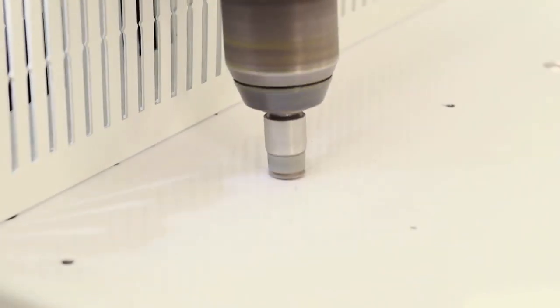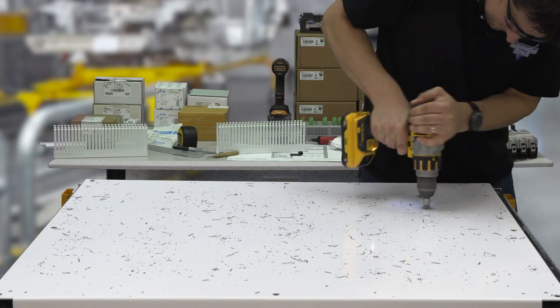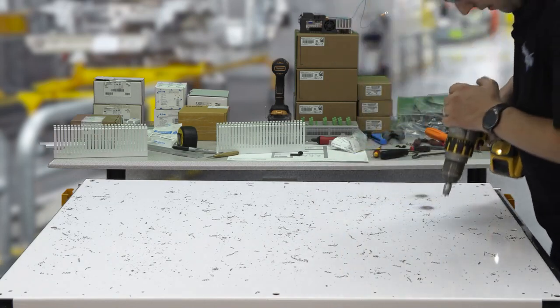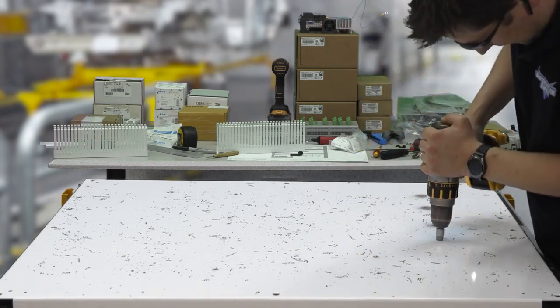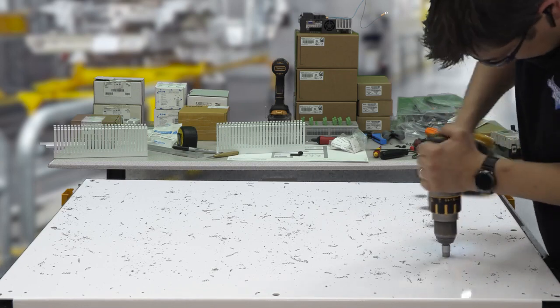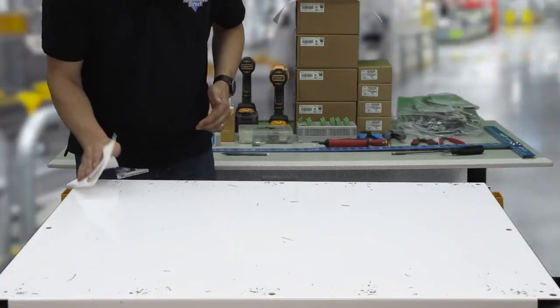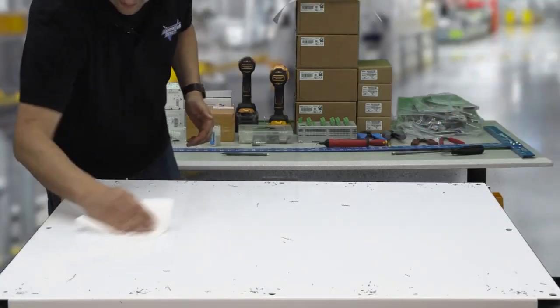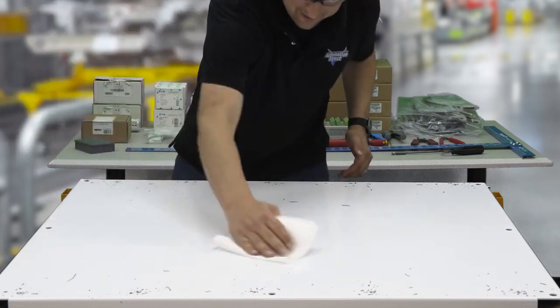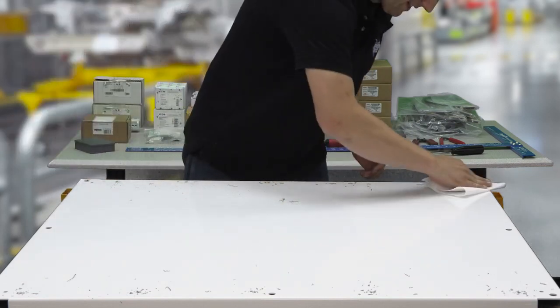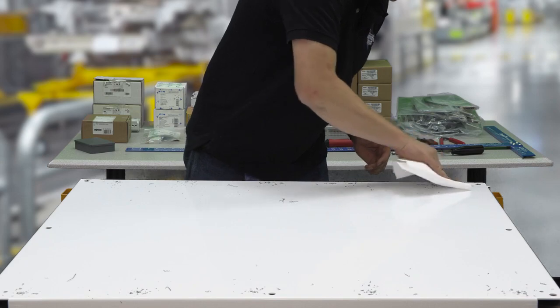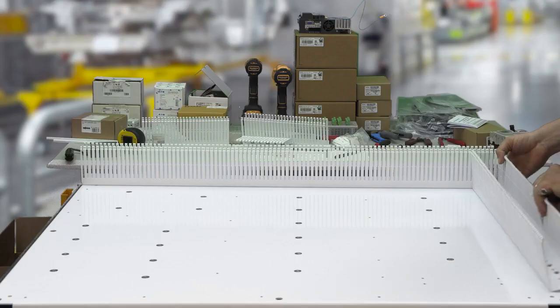Now that all of your holes are drilled, tapped, and deburred, use a bonding brush to remove any paint around the holes that will be used to attach DIN rail, as well as any non-DIN components that require a case ground. Carefully wipe off any metal shavings from the panel, then use WD-40 to remove any remaining pencil marks, and finally use isopropyl alcohol to clear any remaining residue and allow the panel to air dry. Now it's time to start adding parts to the panel.